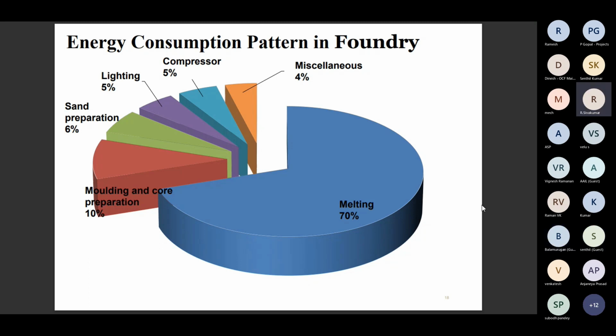So the next one is Foundry, best operating practices in melting. This general diagram, all the foundrymen know about this Pareto analysis chart. So in the foundry, basically in an induction foundry, 70% of the energy is used by the melting section. The remaining 30% of the energy is utilized by the auxiliary loads, like compressor, molding and core preparation, sand preparation, lighting, and other pumps and cooling systems. These are all the various consumers. So 70% of the total energy consumption by the unit goes through the melting section only.